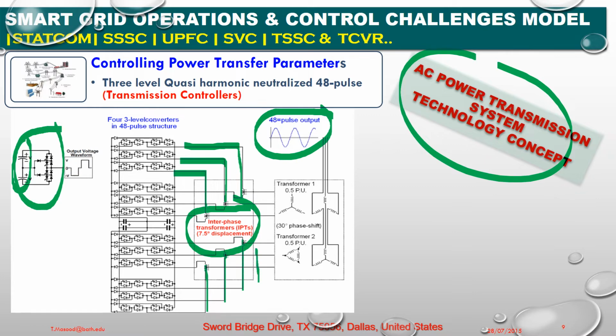The other two phases, as I have demonstrated here, would be connected across the same DC bus bar, and the clamping diodes connected to the same midpoint of the DC capacitor. It is seen that each half of the phase leg is split into two series connected valves, as we have seen here. The midpoint of the split valve is connected by diodes to the midpoint as shown. This may seem like doubling the number of valves from 2 to 4 per phase leg, in addition to providing 2 extra diode valves.